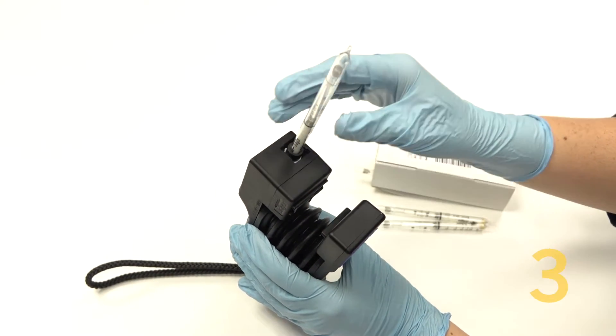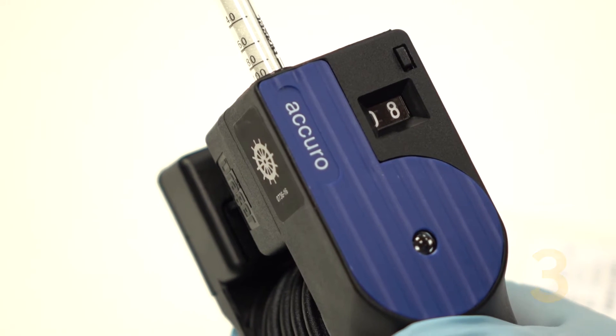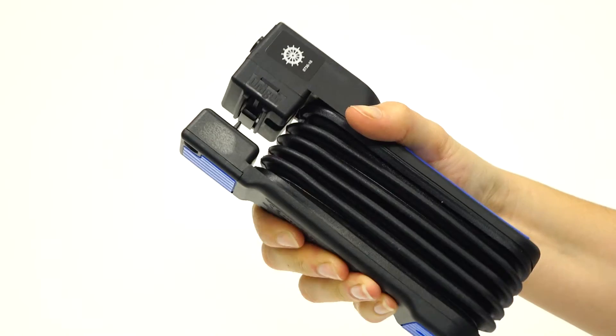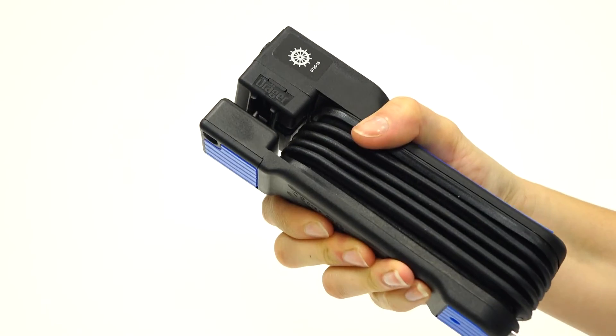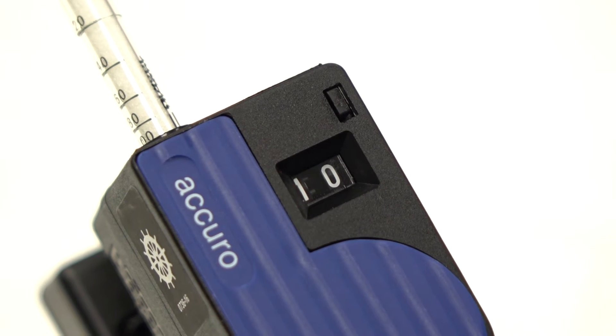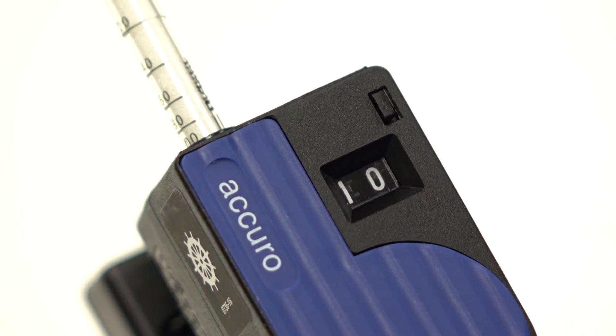Number three, the amount of times the pump is squeezed is known as strokes. The number of strokes depend on the type of tube being used and also the measurement range required. Some tubes even require 100 strokes. Luckily, the Accuro pump comes with a stroke counter, making it easy to keep track.